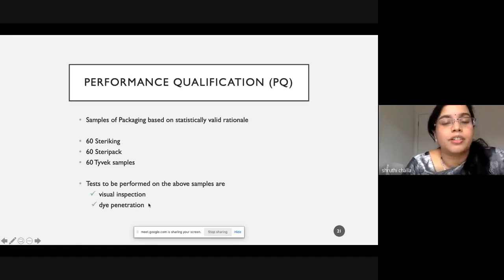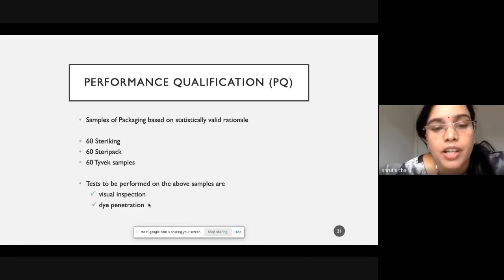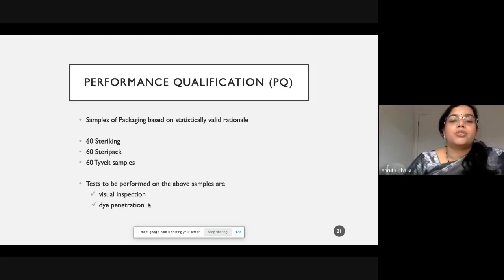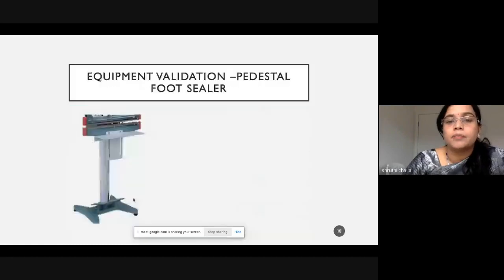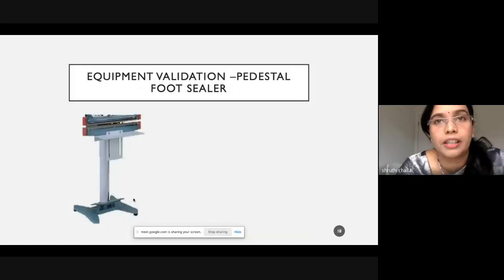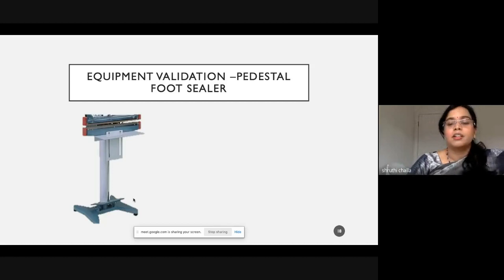There are two different tests here, visual inspection and dye penetration. We check all the samples for these two tests, and we check whether they have passed or not before we start using it for sealing the actual devices. Actually, this particular equipment we use for sealing of sterile medical devices. I have taken this because it's a very simple example and helps you understand the equipment validation.